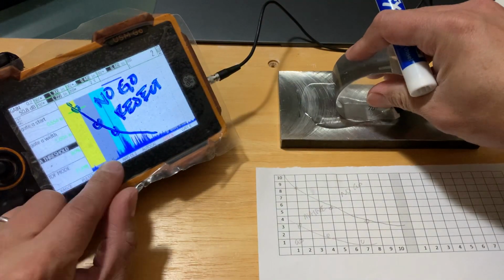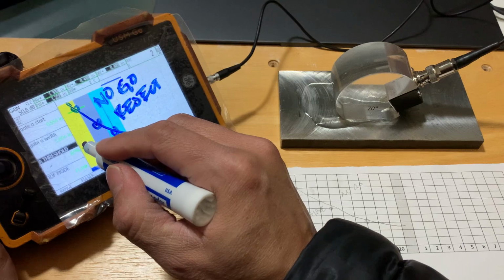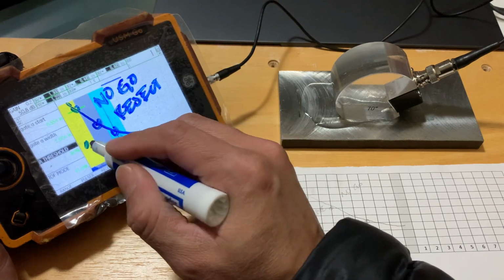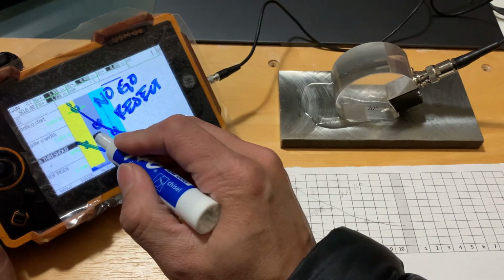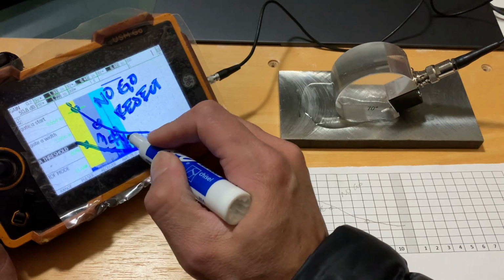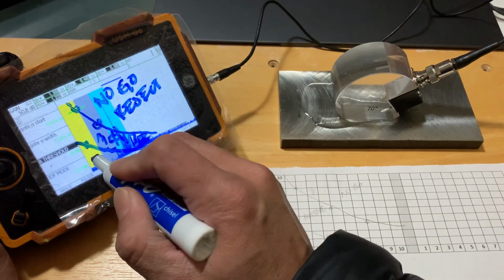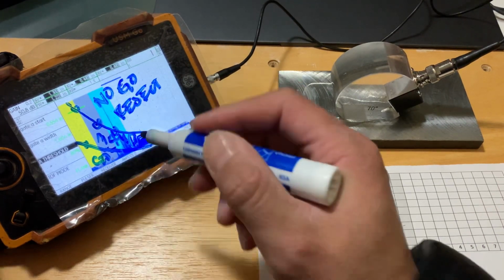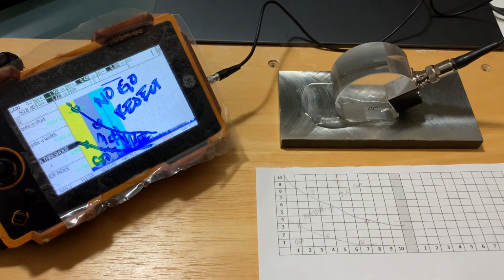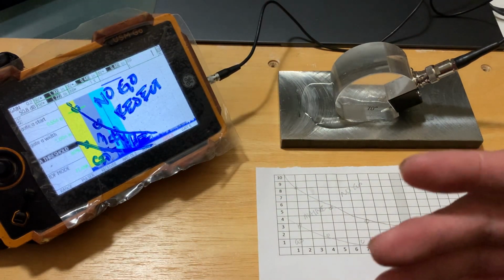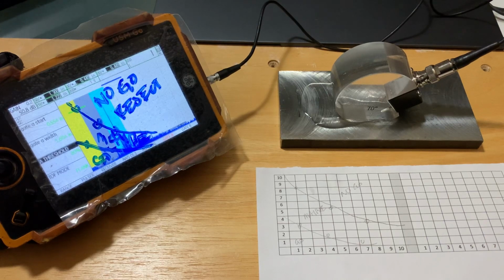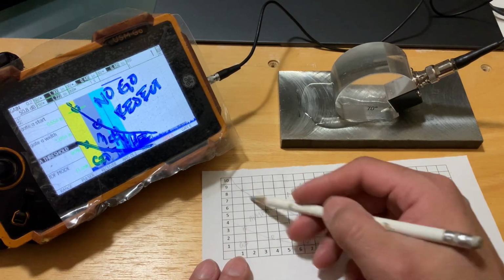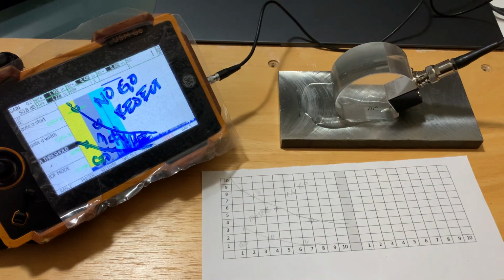If you have other indications down in here, if we do the 6 dB drop and it's within that, then this is a maybe. Anything down in here is a go. So like I said, essentially it's a calibration within a calibration, and it's supposed to speed up your evaluation time. And you'll plot it just like how I did here, just like on the screen. And that's a DAC curve with a shear wave.